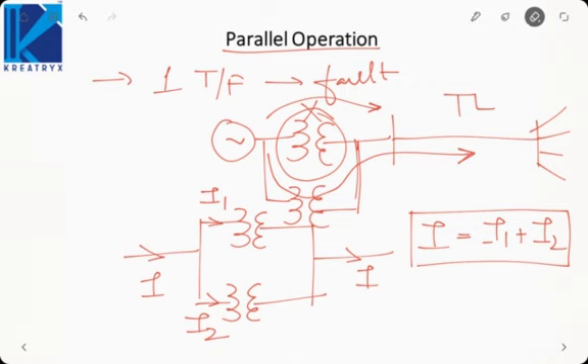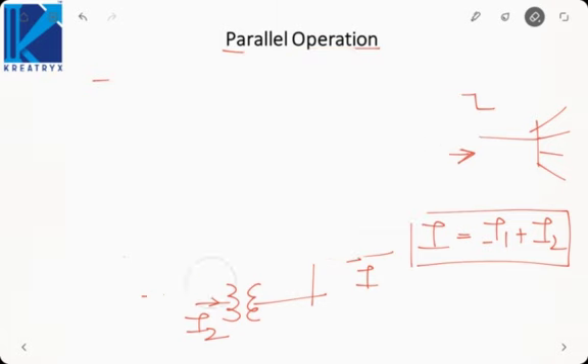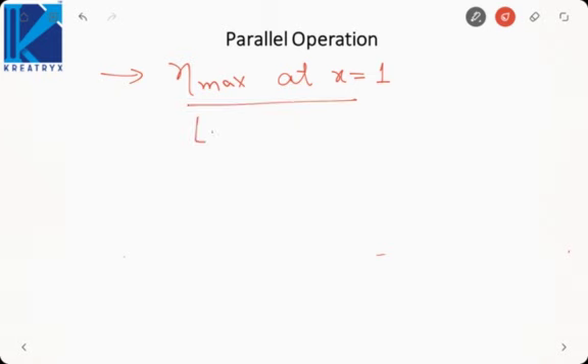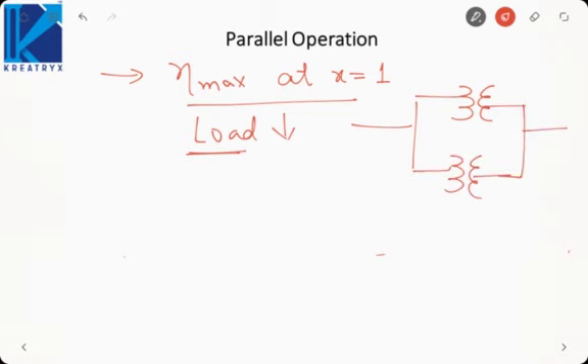Okay. Other thing is that we know that a power transformer operates at maximum efficiency when it is fully loaded. I told you a power transformer is fully loaded during the entire 24 hours a day. So a power transformer has maximum efficiency at full load, that is x is equal to 1. Now suppose due to certain problem load decreases at certain point. Then if two transformers are sharing the load, then what will happen? Both will be away from full load. Now none of the transformers will operate at full load. Suppose 0.7 times full load current is coming. This current will be divided amongst these two transformers. None of the transformers will operate at full load. That is, none of the transformers will be operating at maximum efficiency. Because for a power transformer, maximum efficiency occurs when it is under full load condition.